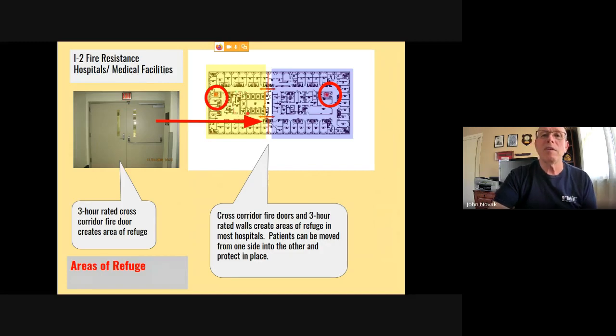We may have an elevator, right? Elevator could be used if it's determined that it's safe to evacuate patients if it comes down to that. But with the fire resistance, if the fire resistance is maintained here, this area of refuge should suffice until the issue is contained over here. Because remember, we're talking about a medical facility. More than likely, at least newer facilities, are going to be fully sprinklered. So the sprinkler should control just about any fire situation, or at least keep it in check until the fire department can respond and complete extinguishment.